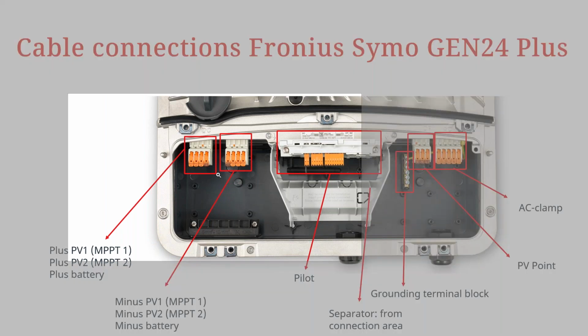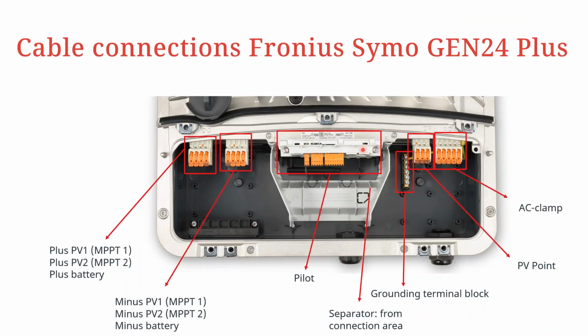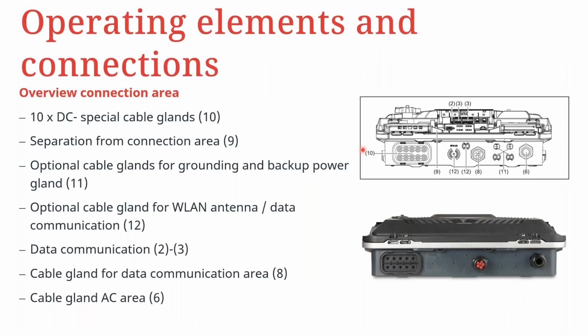We have 2 strings and 1 string on the positive connection from the PV array, and then the positive connection for the battery. And then on the second connection for DC, we have the negative connection, whereby we have the battery, PV2, and then 2 strings for PV1. So that's as far as the connections are concerned. Then if we go further, we look at the specifics about the connections and how these are achieved.